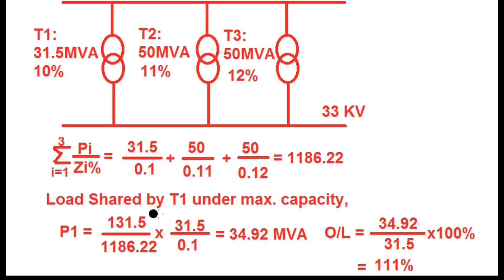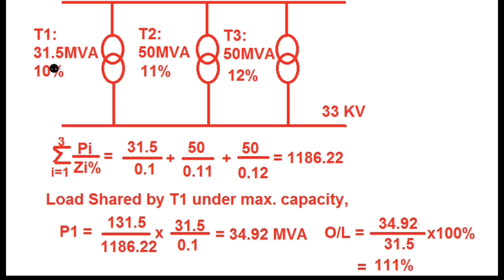We can now calculate the load shared by transformer 1 under maximum substation capacity of 131.5 MVA. P1 = (131.5 / 1186.22) × (31.5 / 0.1), which gives P1 = 34.92 MVA. However, the maximum capacity of T1 is 31.5 MVA, so it will be running under overload condition at 111%.